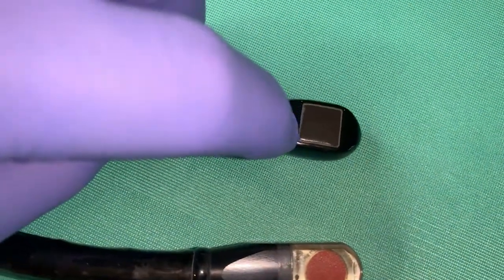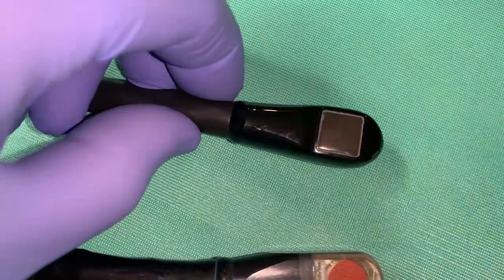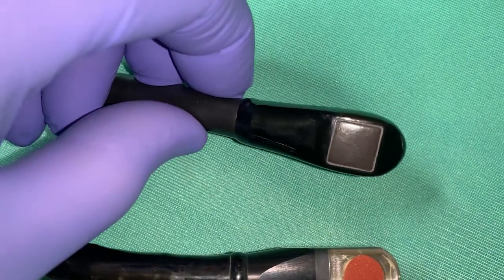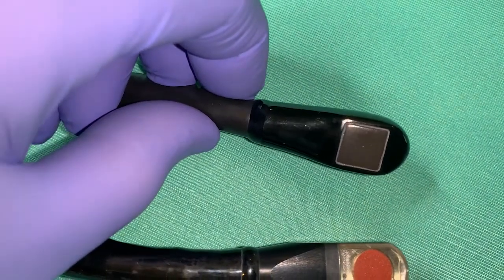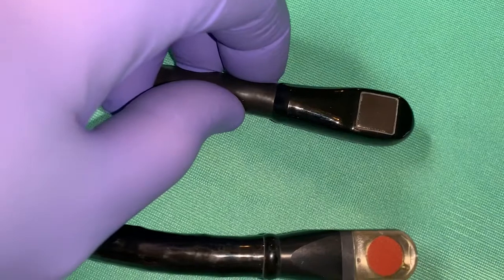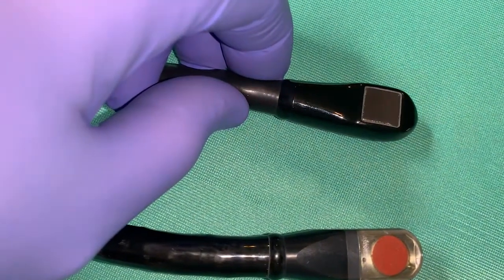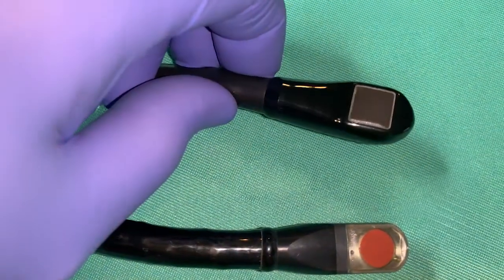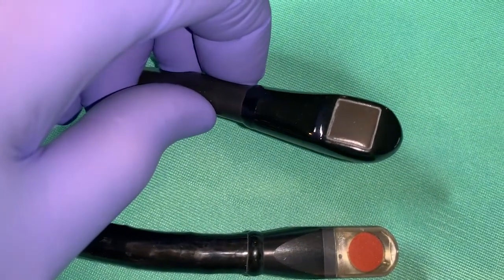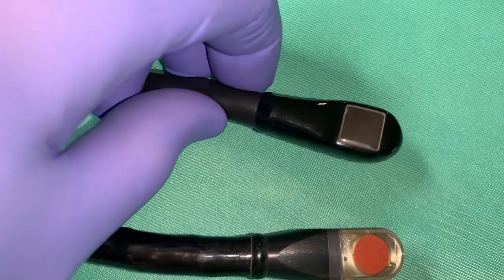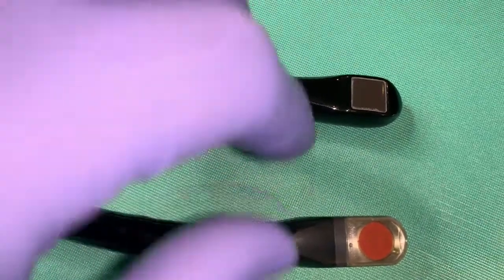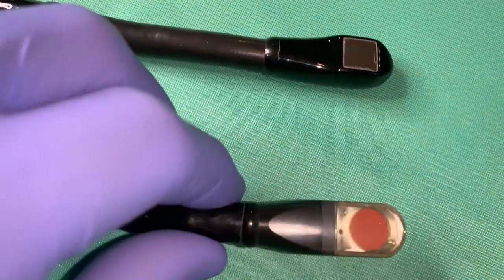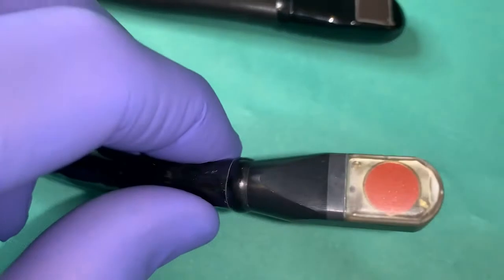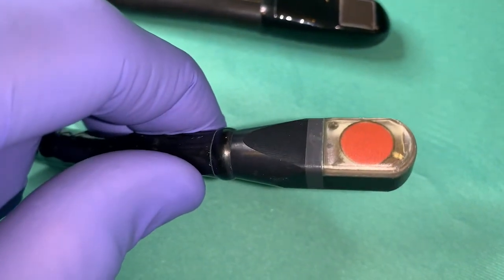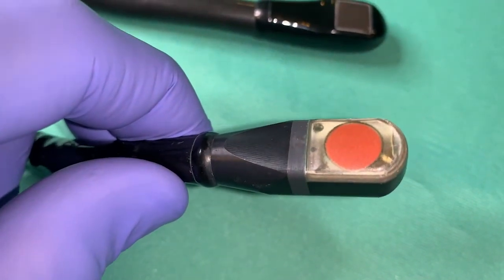Inspect the lens for deep scratches or gouges and examine the seal under magnification for any kind of inconsistencies or lack of fill. The lens on Philips T-probes is coated with a clear coating that will peel away over time and may appear fractured. This would be considered acceptable and could be considered part of normal wear and tear. The peeling or the lack of the clear coat does not affect performance and poses no safety risk.